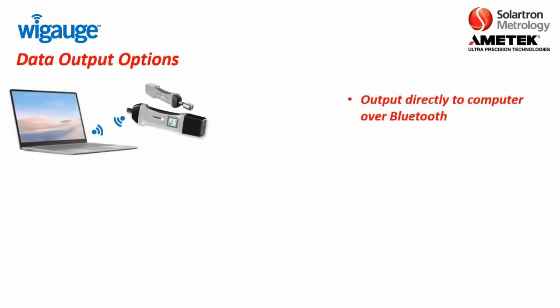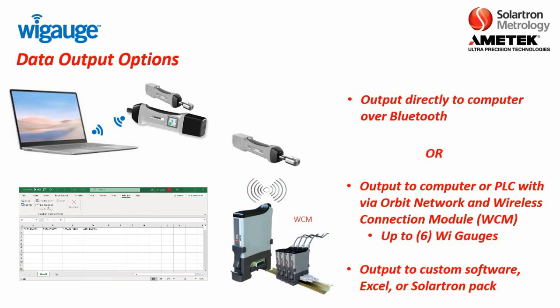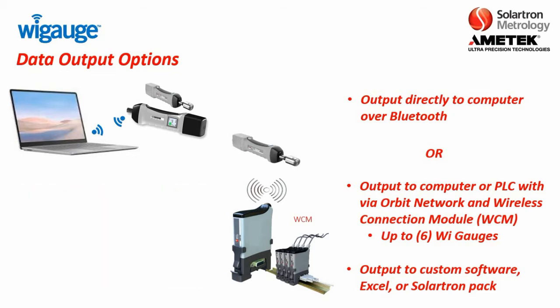In terms of data output, you have one of two options. The first is where you can output readings from the WiGauge directly to a computer via Bluetooth. Or you can output to a computer or PLC via the Orbit network using the wireless connection module, where you set up the WiGauge with the wireless connection module and data flows through there. With this, you can connect up to six WiGauges per connection module. You can output to custom software, Excel, or Solartron-provided software such as Orbit GCS.